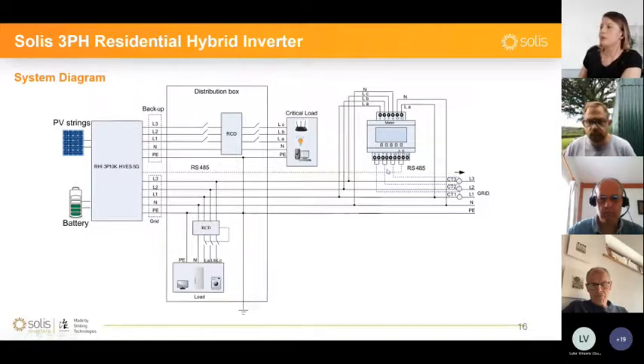This one comes with, of course, 3 CT clamps, one for each of the phases. For powering up the meter, you have the pins 13 and 12, and these will help supply the meter with the power. And for measuring the voltage on each phase, there are pins 1, 2, and 3, and the neutral on pin 4. All these connections need to be done correctly in order for the meter to get all the data needed for the inverter to work.